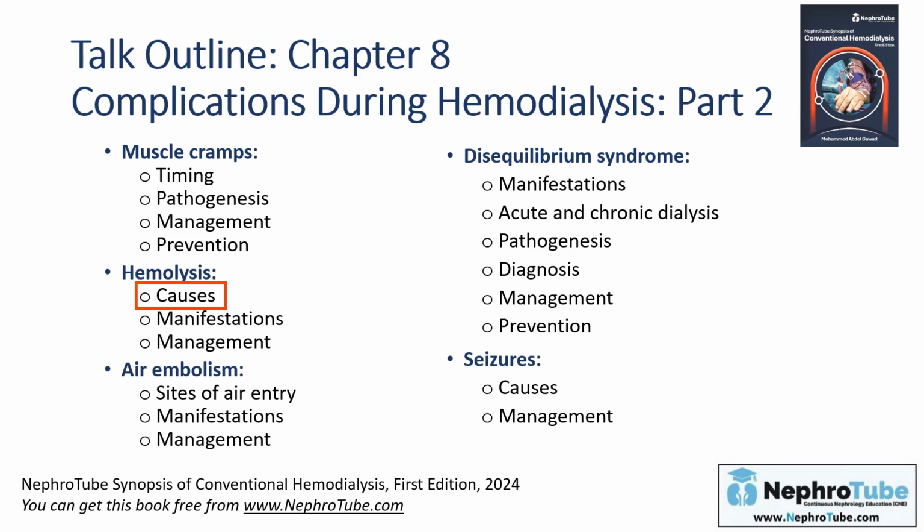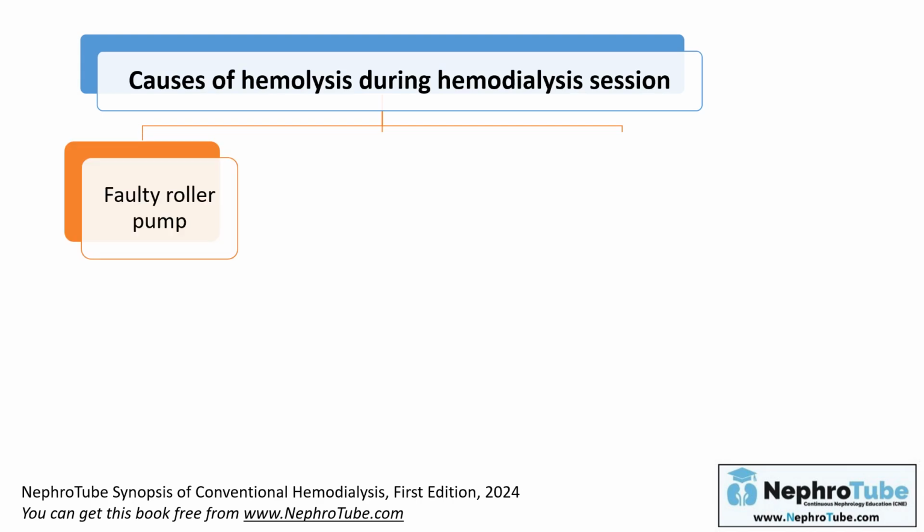Hemolysis is a rare condition in hemodialysis, but it may be fatal on some occasions. What can cause hemolysis during a hemodialysis session? First of all, a faulty roller pump. There is a problem in the blood pump where it compresses the tubing set very hard, causing destruction of red blood cells and hemolysis.